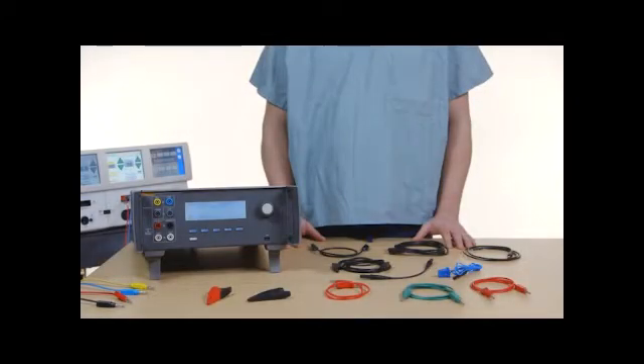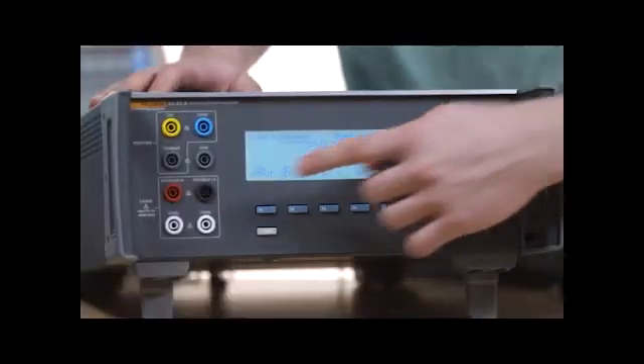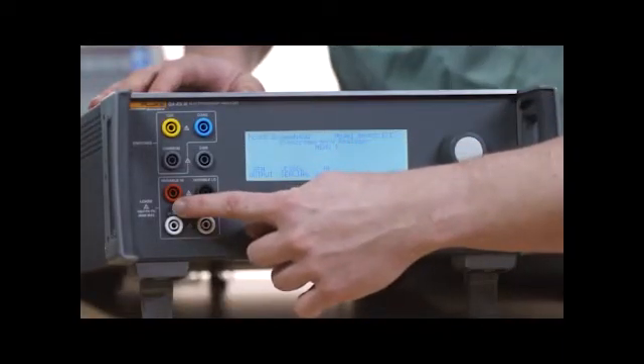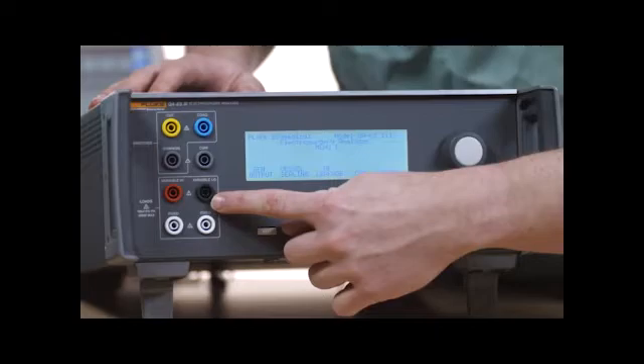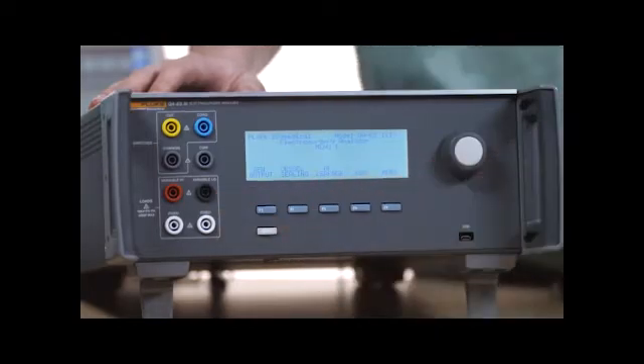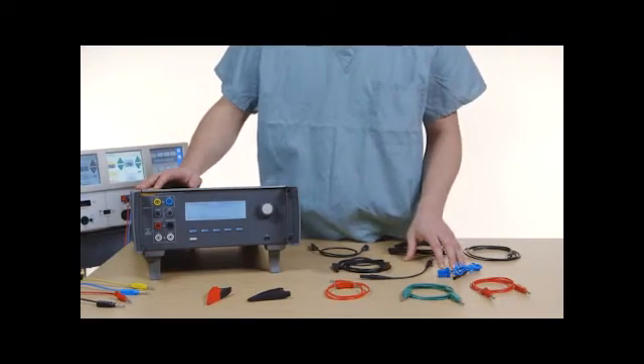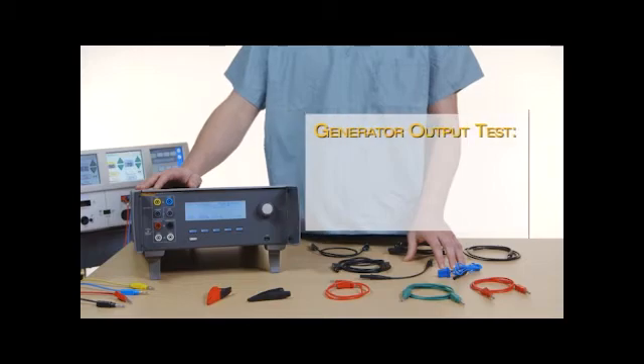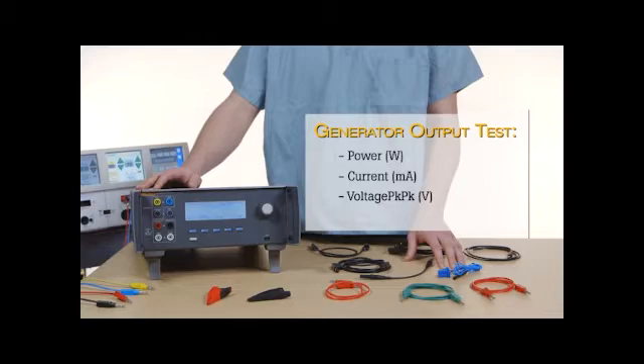During the generator output test, the QAES3 connects the variable load resistance from the variable high active electrode to variable low neutral electrode. The test measures the ESU output across that load and shows the measured generator output power, current, voltage peak-to-peak, and crest factor.